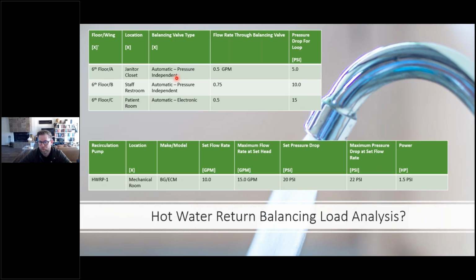because if the owner needs to go back and modify a hot water recirculation system for a hospital, let's say they're adding 3 new loops, those loops should be checked against the overall system, to make sure that the existing system has capacity, both the pump and the pipes, that you're not exceeding velocity limits in the piping system, and that your pump has the capacity to take on the additional load, much like what we do when we size our incoming water mains, and also much like we do when we're doing electrical load analyses.